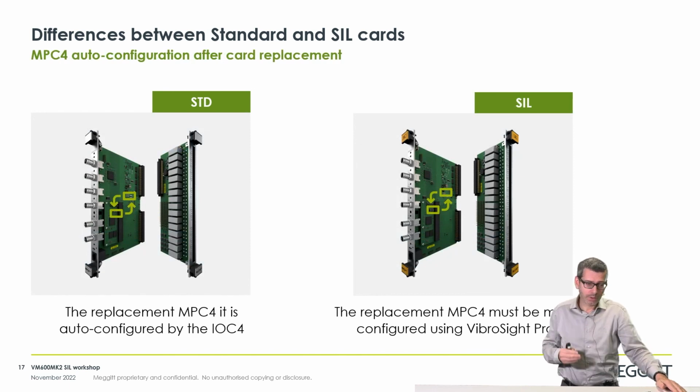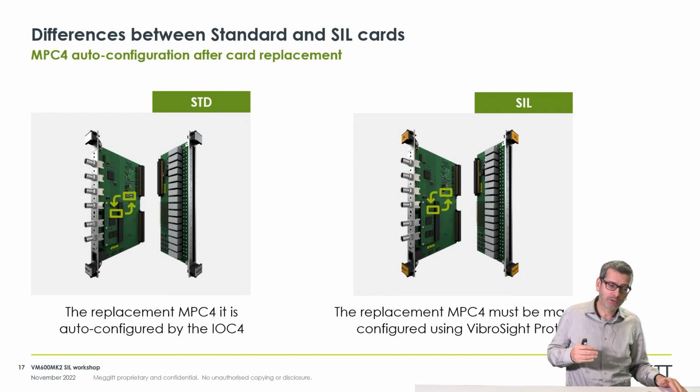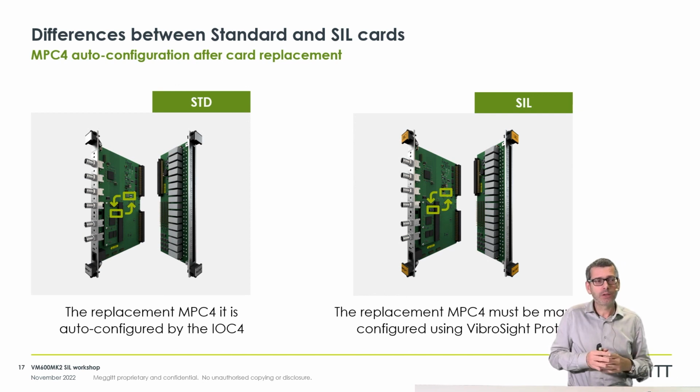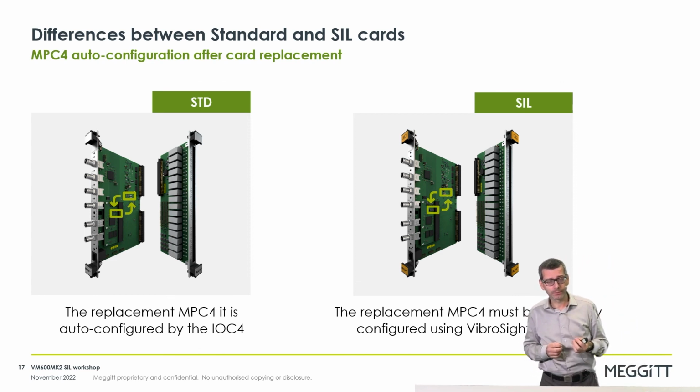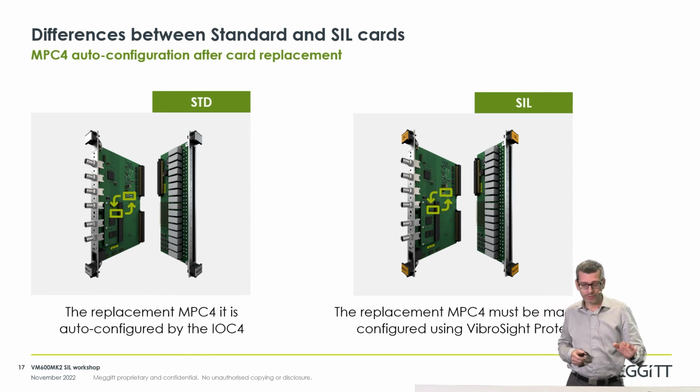In the MPC4 standard, there is one interesting feature, which is the fact that the protection configuration is stored on the IOC card itself. There is a memory on the IOC where the configuration is stored. That means that if the MPC4 fails, it can be directly replaced, and the IOC4 will configure the MPC4.